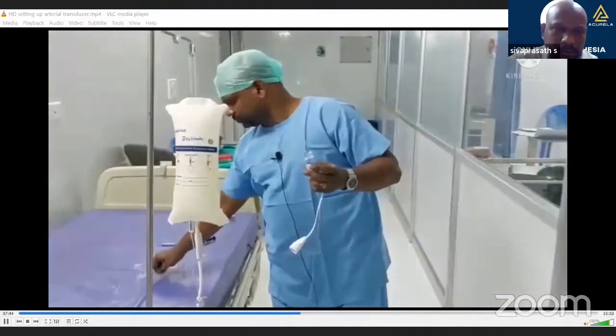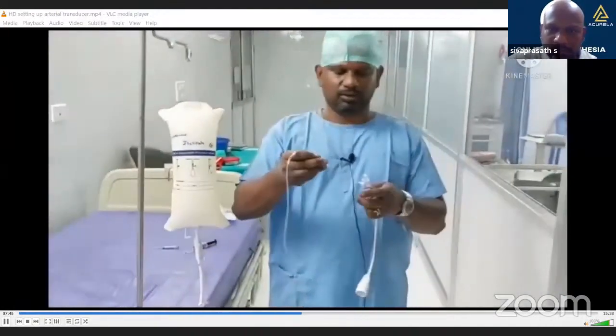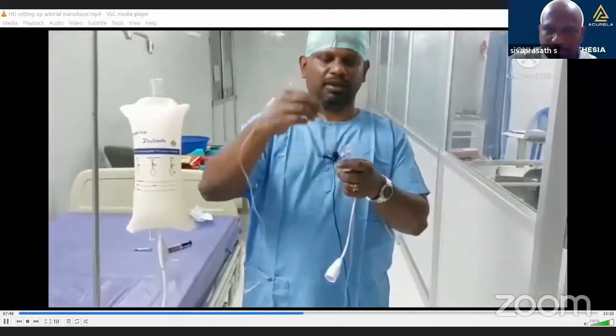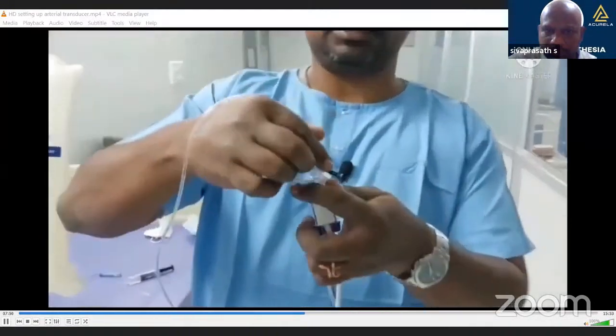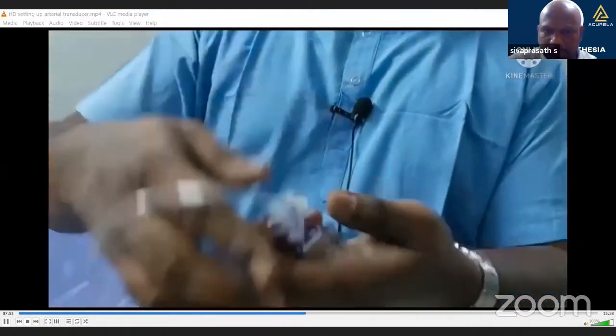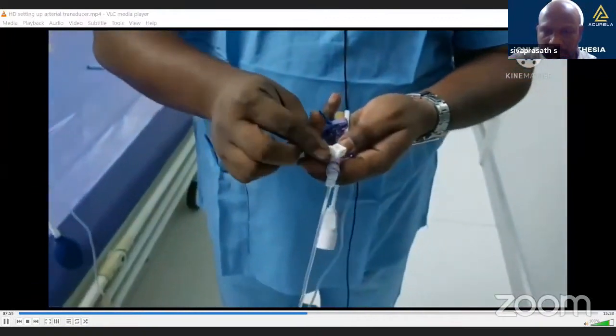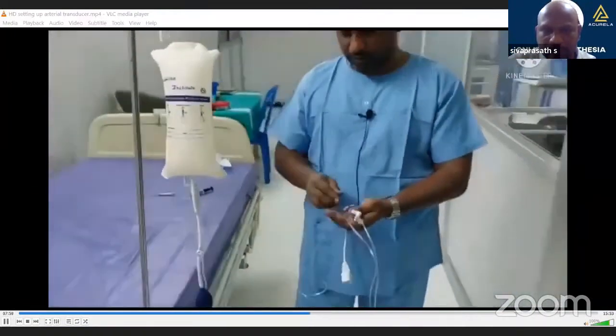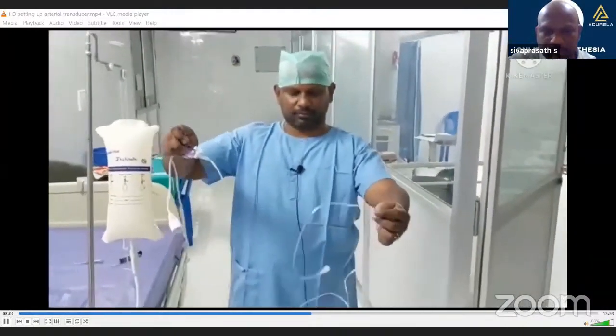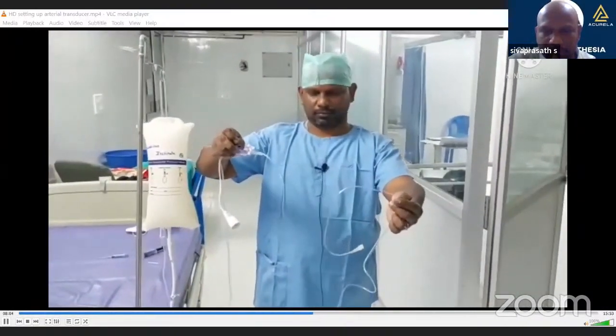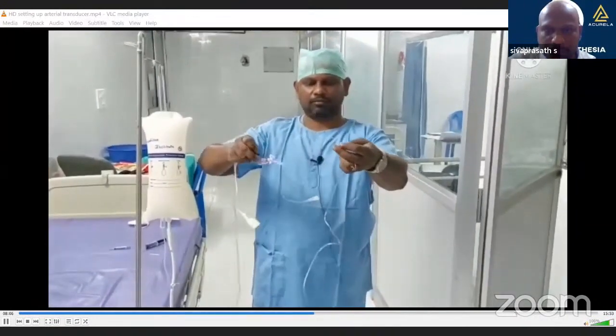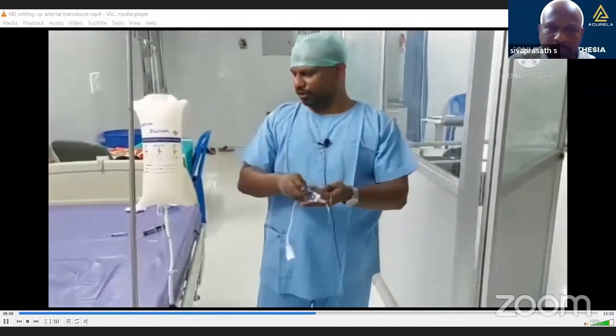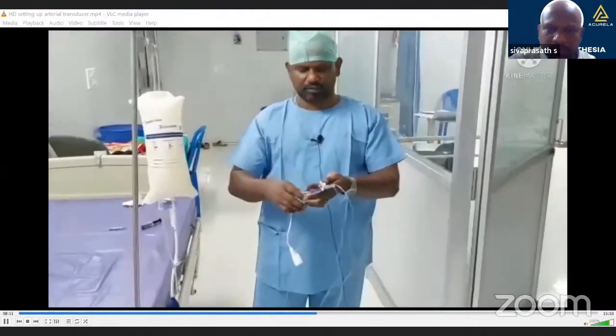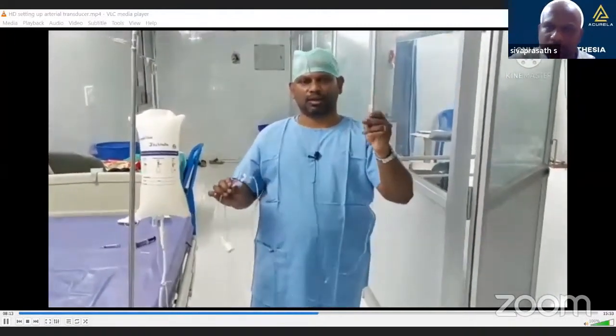Now I have to connect the connecting tubing to the patient end. This is the female end. I'm connecting it to the patient end, tightly tapping it and changing the stopcock towards the patient end, and again de-air. So you can see it has come up. There is no air from the pressure bag system, the transducer, and to the connecting system. There is not even a single bubble of air in it.